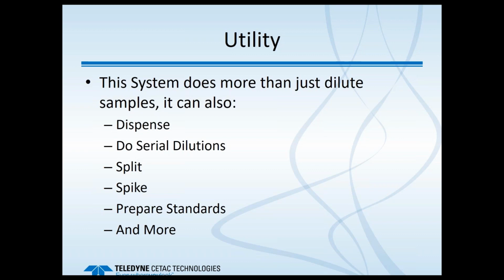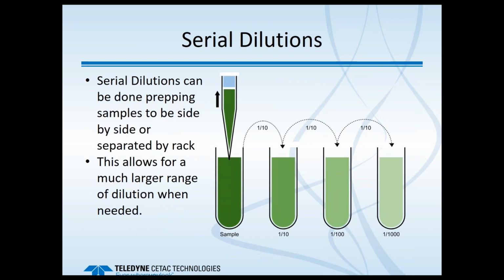So if, for example, you wanted to prepare samples for your ICP-MS, your AA, and your IC, you could have the same sample prepped 3 different ways across 3 different racks, and then rack 1 goes to instrument A, rack 2 goes to instrument B, and rack 3 goes to instrument C. It can also do standard spikes, and it can prepare your calibration curve. So a few specific applications that I thought we'd go into a little bit more in detail.